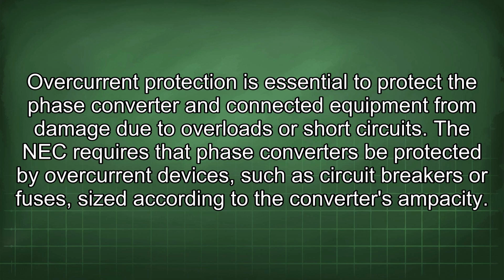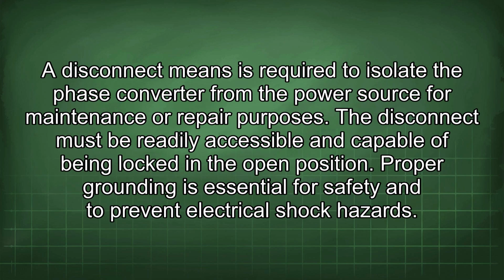The NEC requires that phase converters be protected by overcurrent devices, such as circuit breakers or fuses, sized according to the converter's ampacity. A disconnect means is required to isolate the phase converter from the power source for maintenance or repair purposes. The disconnect must be readily accessible and capable of being locked in the open position.